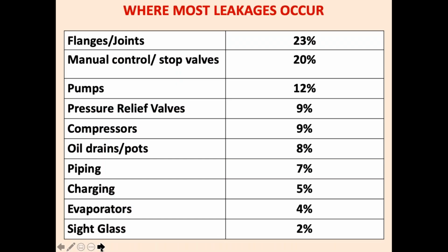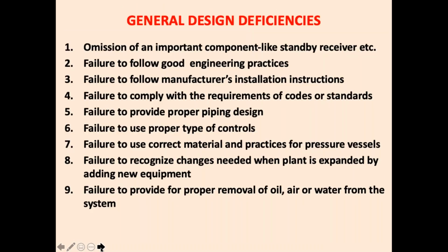This is a global survey which has been done. This is not prepared by me. This is prepared by IIAR, International Institute of Ammonia Refrigeration, and they have analyzed all the accidents and leakages: flanges and joints, 23% leakage; manual control stop valves, 20%; pumps, 12%; compressors around 9%; pressure relief valves leaking, 9%; oil drain pots, 8%; piping leaking, 7%; during charging, 5%; evaporators, 4%; and sight glass accidents, 2%. So these are the various areas which can lead to a leakage.